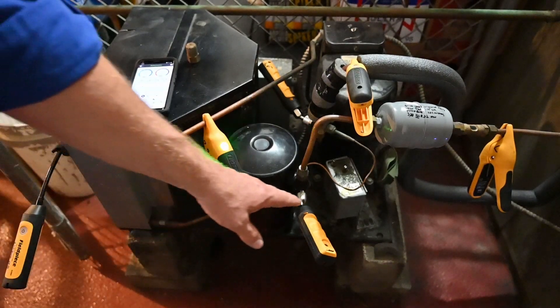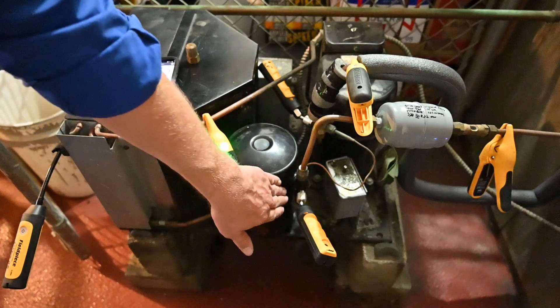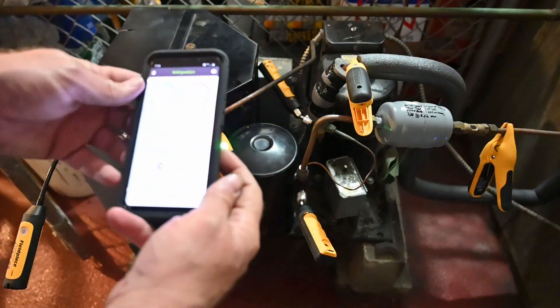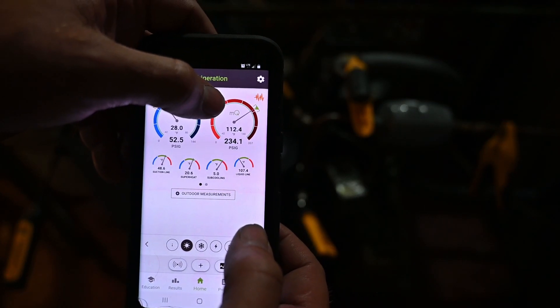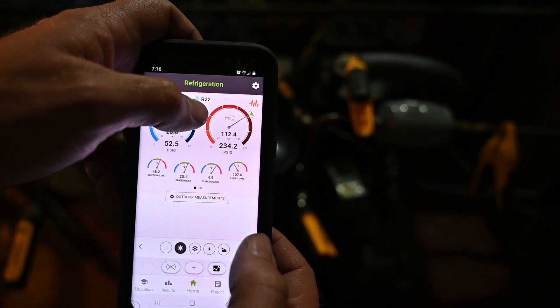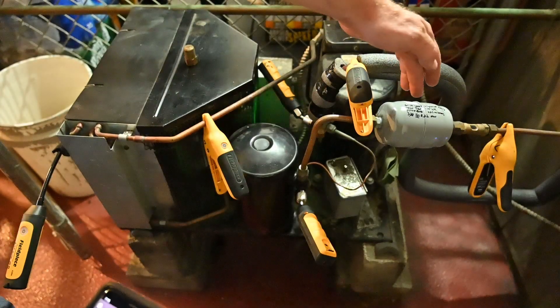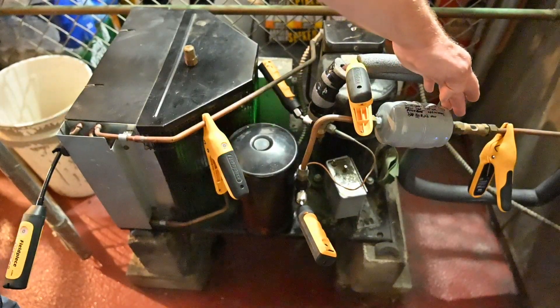We have a probe set up on the liquid side — I know it's the liquid side because it's coming out of my liquid receiver to my king valve. We have this valve mid-seated, giving us our liquid or high side pressure. Looking at the app, it's showing a pressure of 234.2 psi gauge. It's R22, so that's a saturated temperature of 112.4. Following the liquid line over, we see our liquid line filter dryer and sight glass — we want to make sure we have a solid column of liquid.